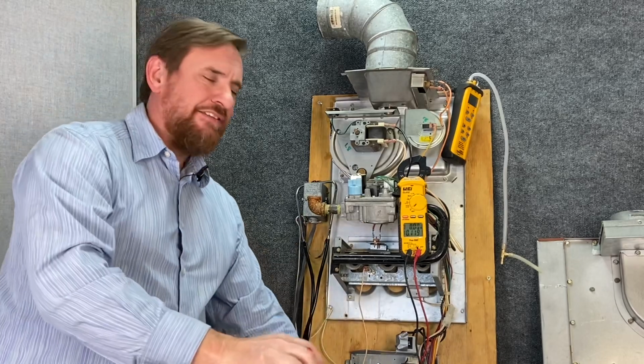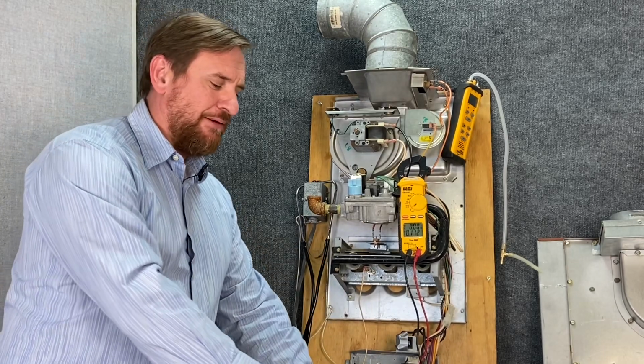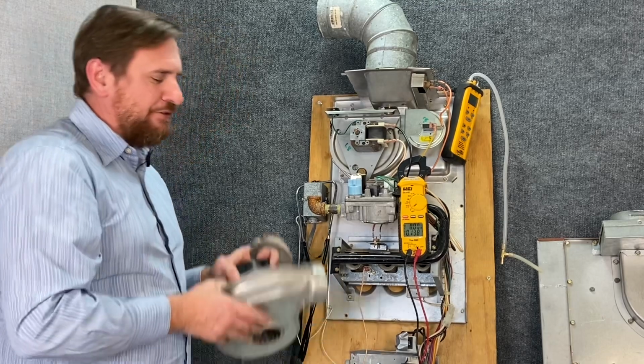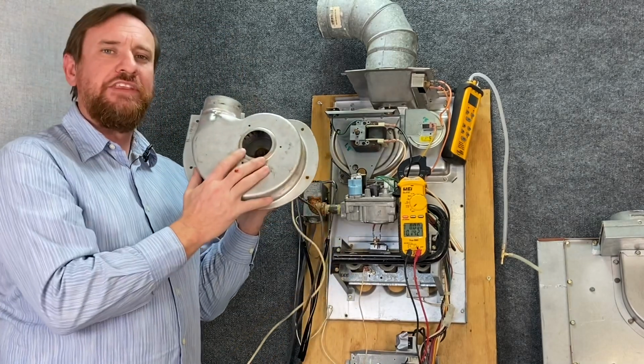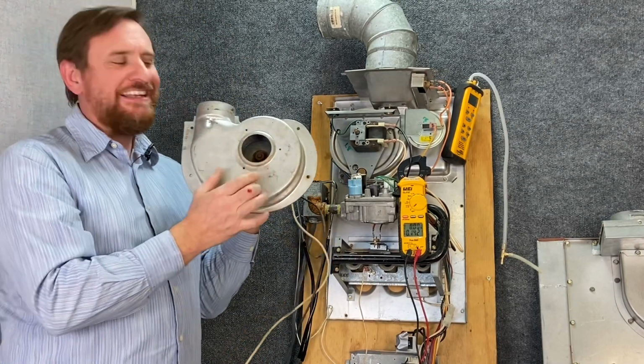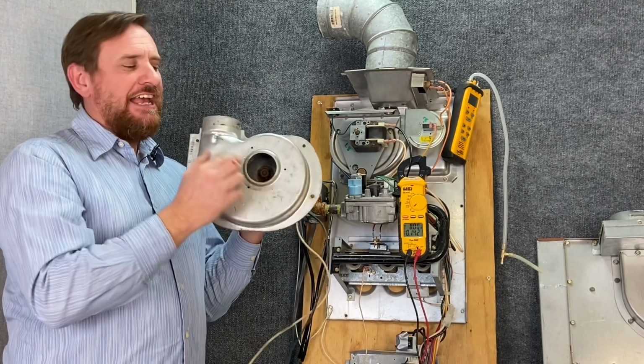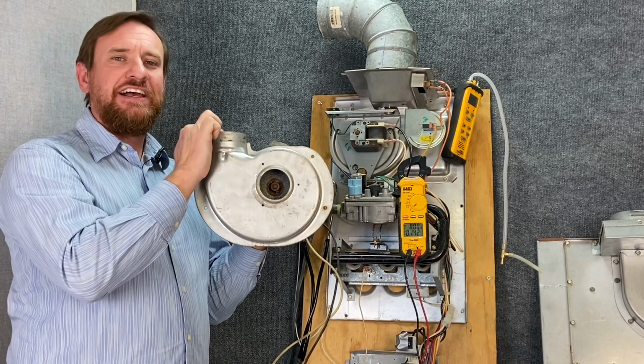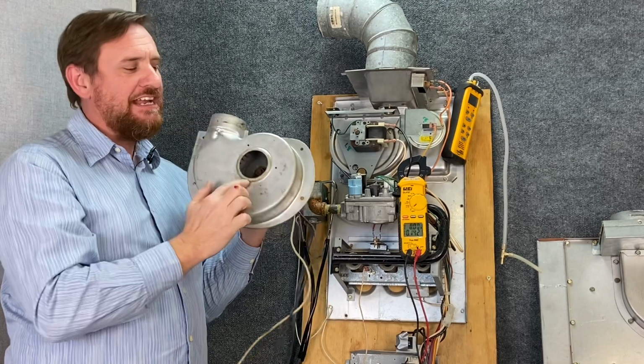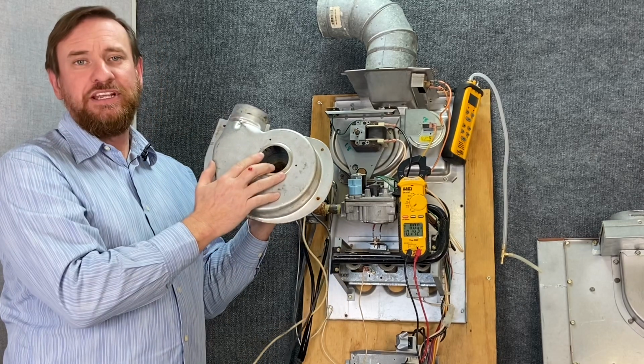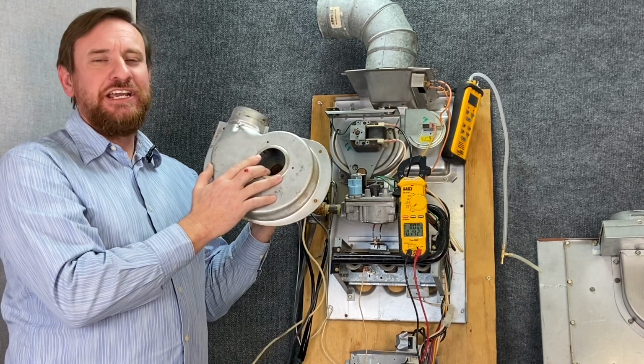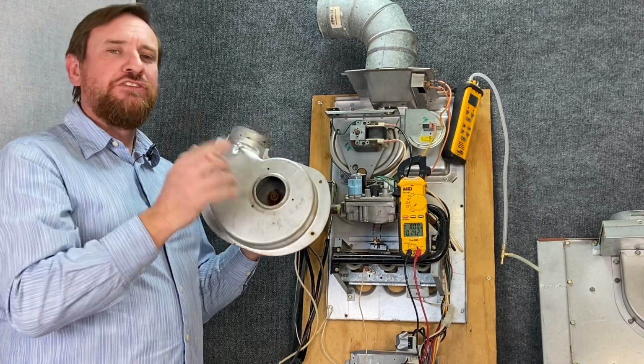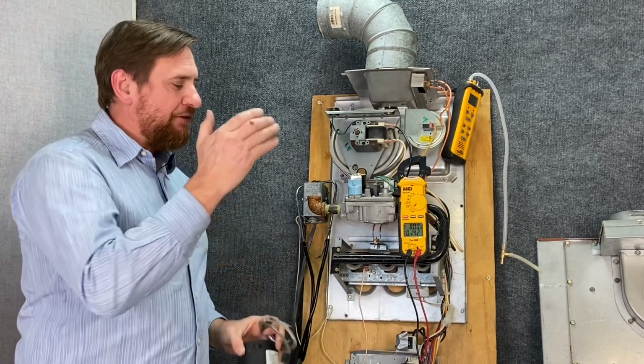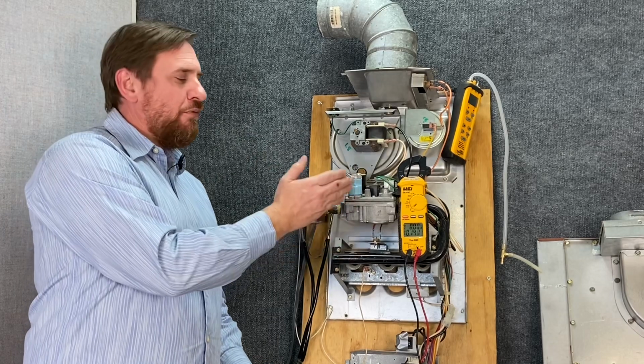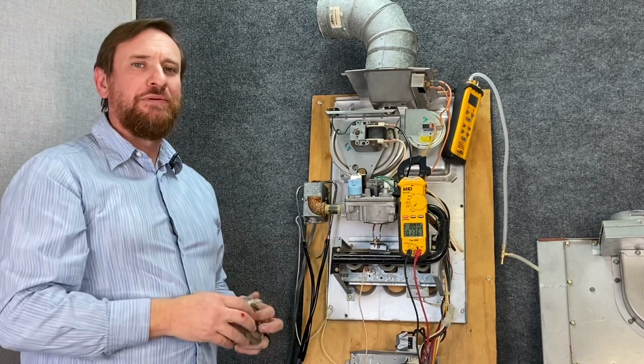As we're talking about these inducer fans, there's something else that's very important. On the back side of this inducer fan, there's going to be a hole. This hole is called a restrictor plate. It's a very precise size. The engineers know the size of the wheel, how fast this wheel is turning, and if they have a set size hole here, they know exactly how much air they're pulling through that heat exchanger, which is very important for combustion. If we know exactly how much air we're pulling through here, we can adjust the gas pressure and get proper combustion.